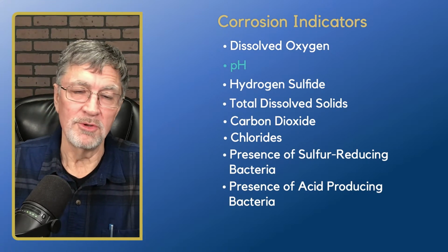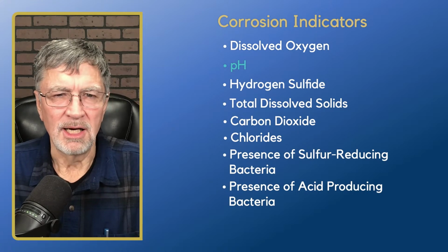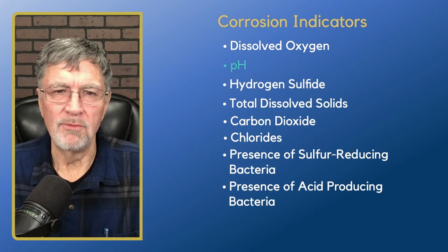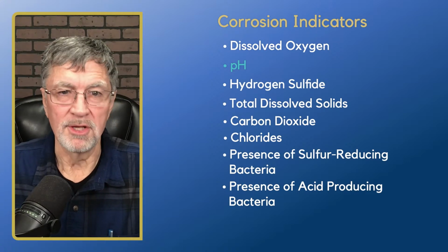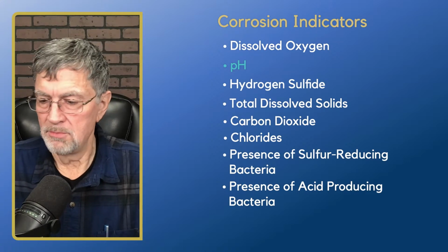So even when we're doing well rehab, using things like hydrochloric acid, we'll tend to use inhibitors to avoid that corrosion from occurring. Even if it's just a brief period during well rehabilitation, it's important to stop that corrosion from occurring. So pH is an important factor there.